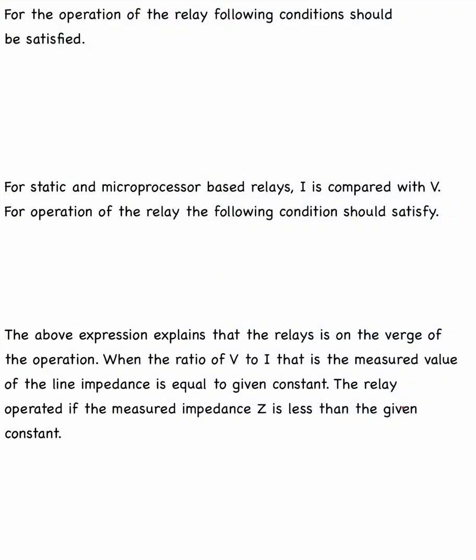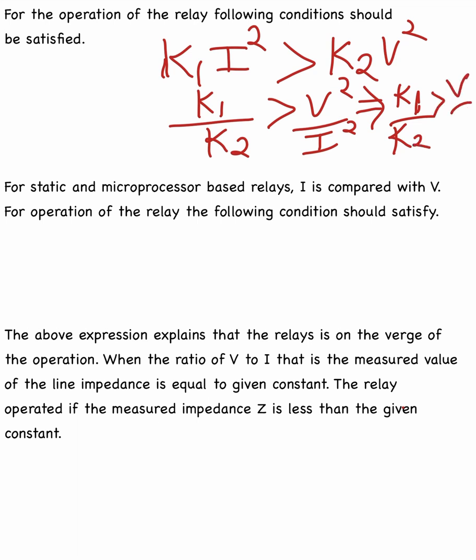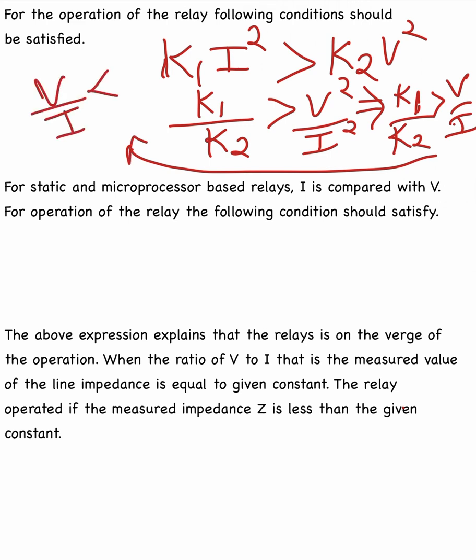For operation of the relay, the following condition must be satisfied: k1·I² > k2·V². This gives k1/k2 > V²/I², which simplifies to V/I < k, and therefore Z < k. This is the operating condition for the impedance relay.